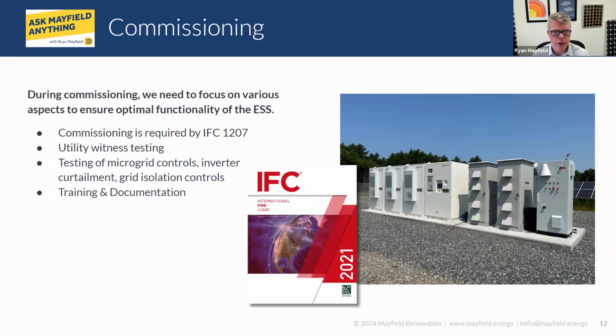I'd also point out, you mentioned IFC 1207 requirement, it's also part of National Electrical Code now in 706. So if you're using a 9540 system and this shows up, it basically says you have to commission it. And then it points to NFPA 855, which has a very detailed list of exact requirements on what that commissioning looks like. So that's probably your best resource when you ask, what do I need to do for commissioning? That would be the place to go.